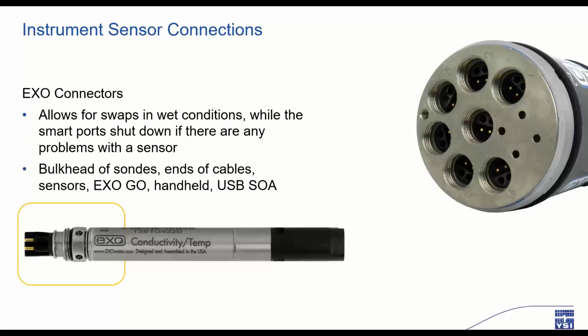A moment ago, we were talking about the connections or connectors that must be kept clean and dry. Now let's talk about the wet mate connectors that are used on all the EXO sensors, sondes, and accessories. We don't have to worry about moisture getting into these connections. They can actually be installed in a rainstorm with no ill effects. The key with the wet mates is to grease the rubber around the connection so that it does not dry out, crack, and peel away from the pins. It is also just as important to remove old grease from ports and connectors prior to installing a fresh coat of grease. Piling new grease on top of old grease can be just as troublesome as no grease at all.